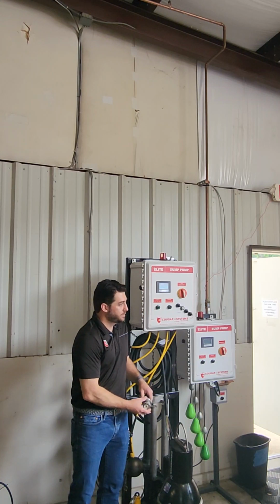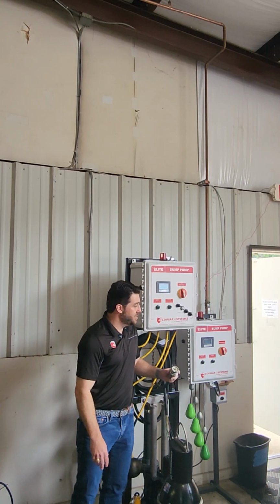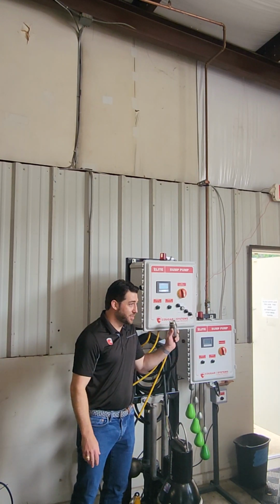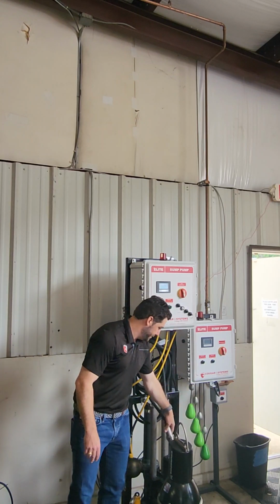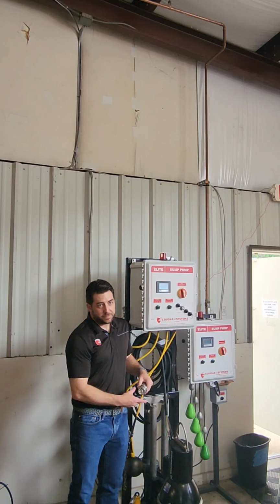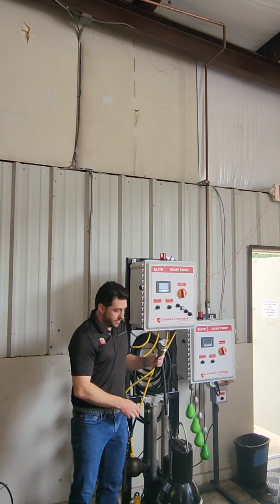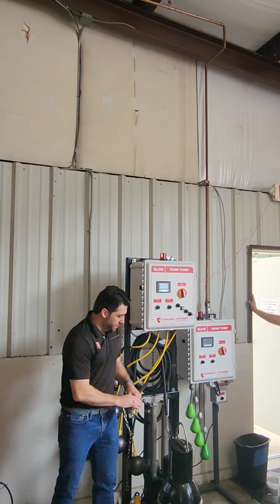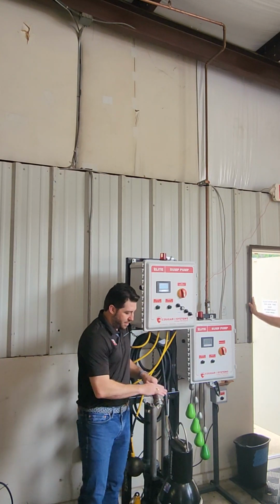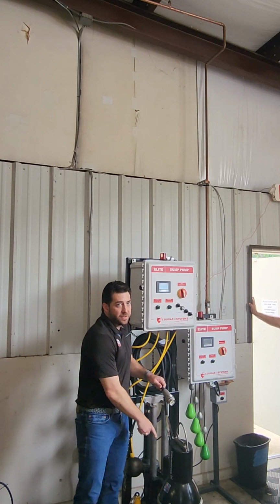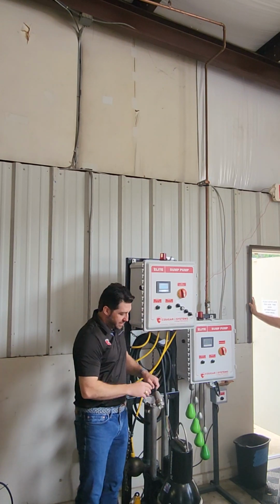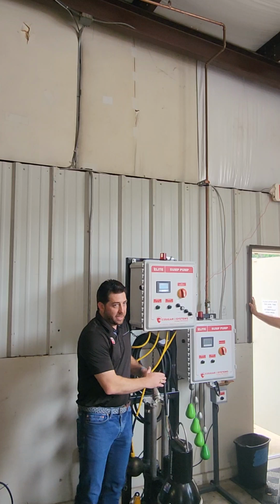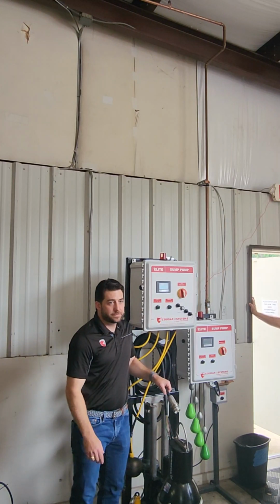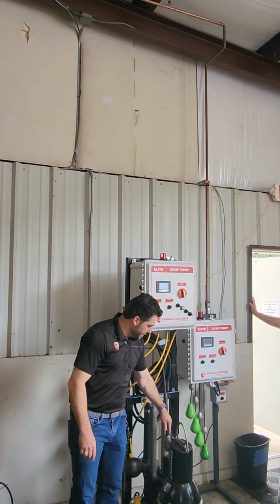Man, just by looking at that, it looks expensive. It is. I'm not going to lie. These are expensive, but it's cheaper than that. What's the selling point? What's the selling difference between these two types of pumps? So this is going to keep a moisture barrier between the cable and the motor itself. Gotcha. So if the panel floods, you just have to replace the cable. You don't have to replace the pump. And the functionality of the pumps or the floats too, right?